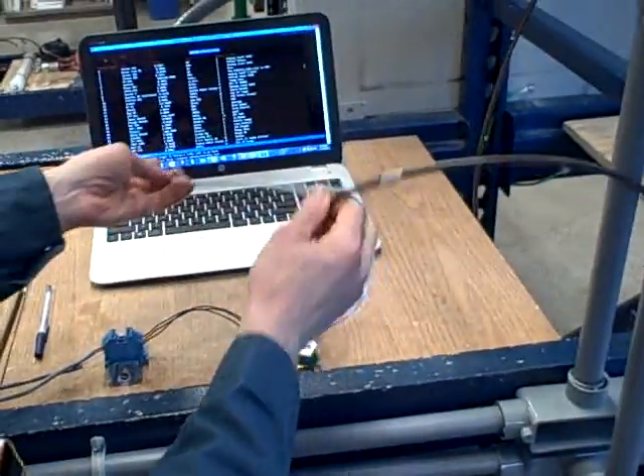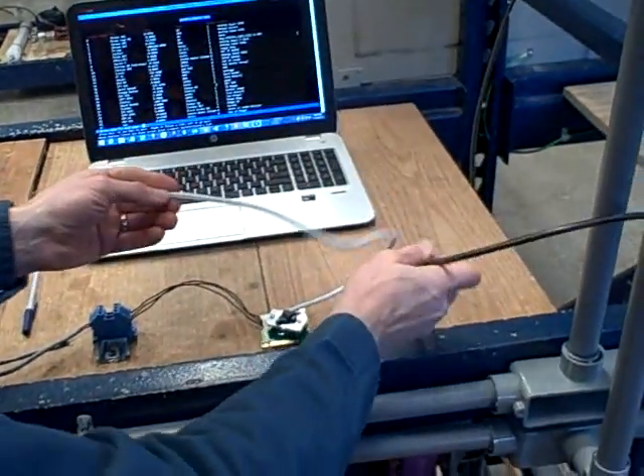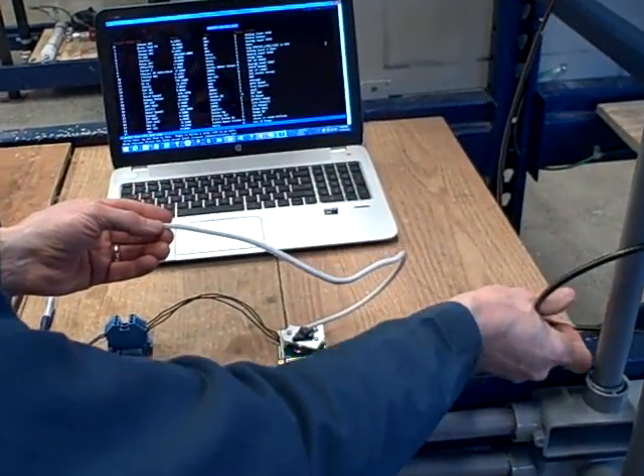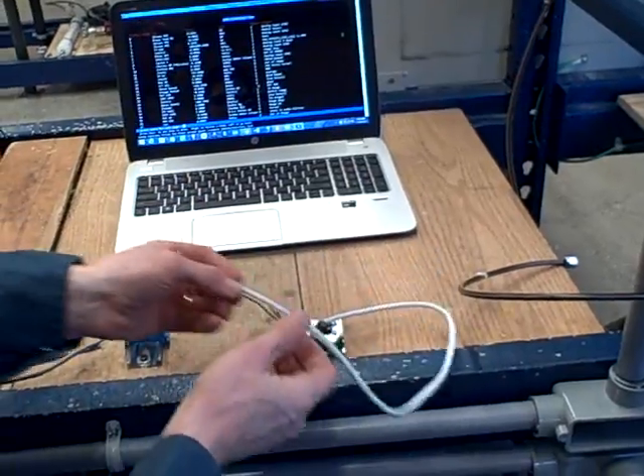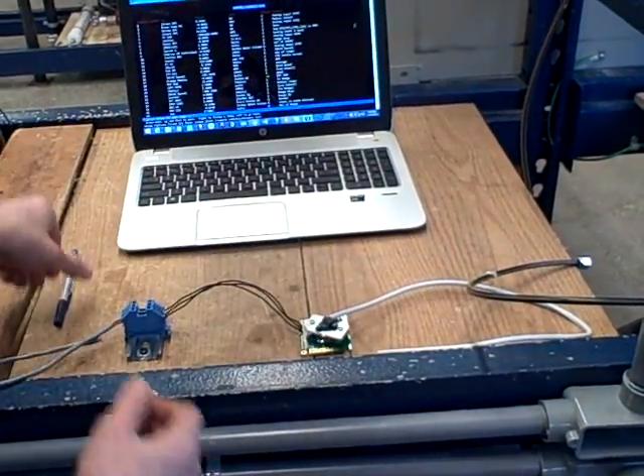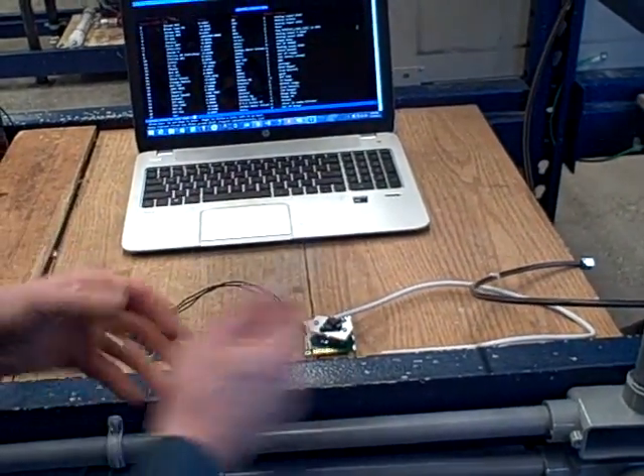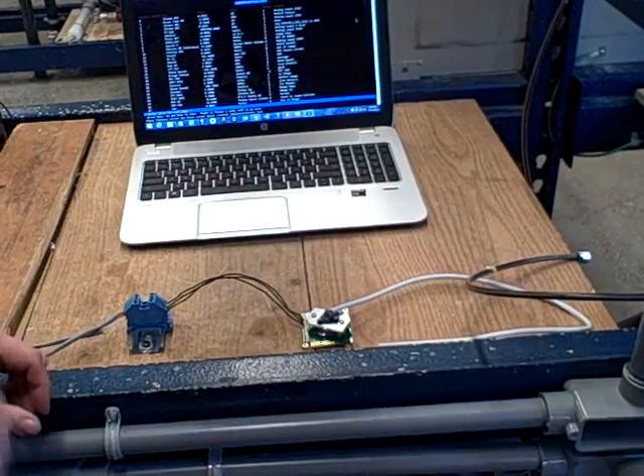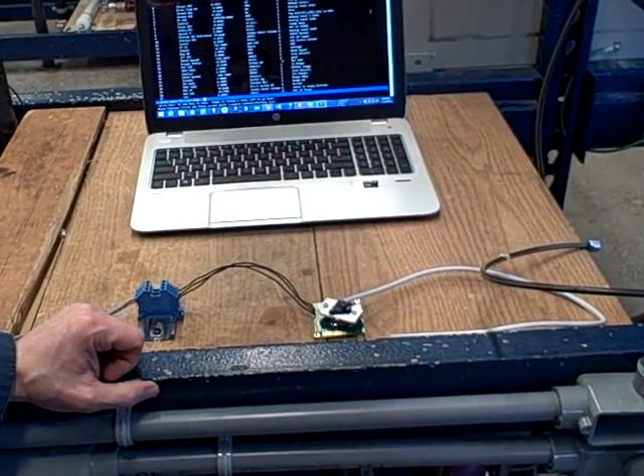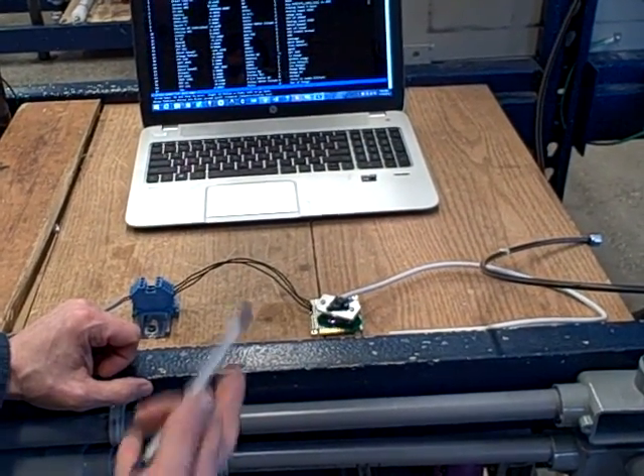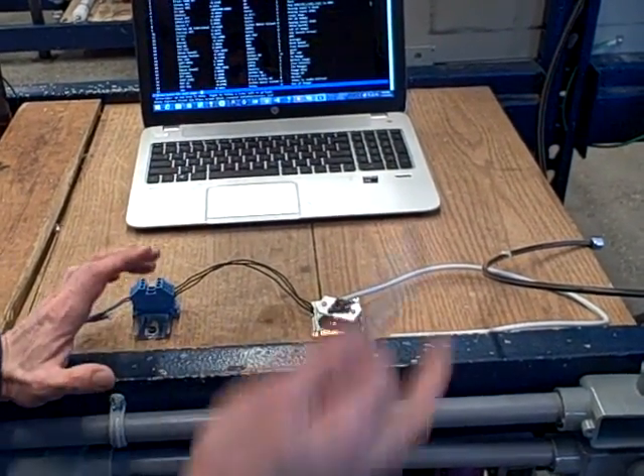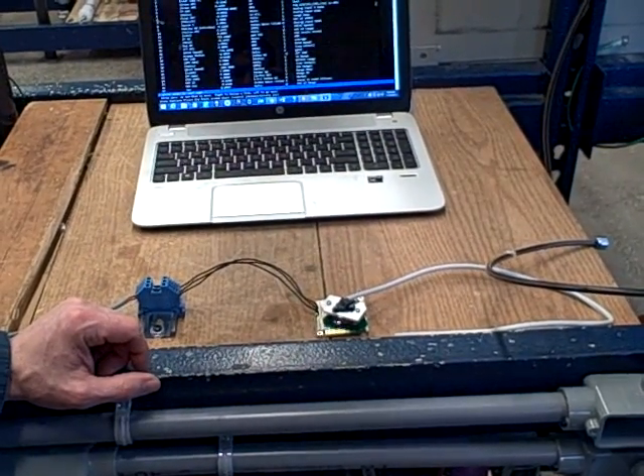What we do for calibration of this is we'll pass a gas sample through the analyzer that contains no CO2 at all. A very easy one is a sample of argon gas used for welding. We'll just get a sample of pure argon, pass that through, and we'll use that as our 0% CO2 reference. And then we can use the atmospheric concentration, roughly 400 parts per million, as our span.